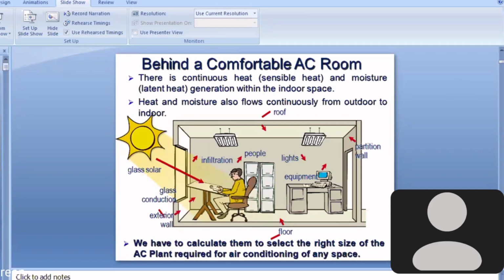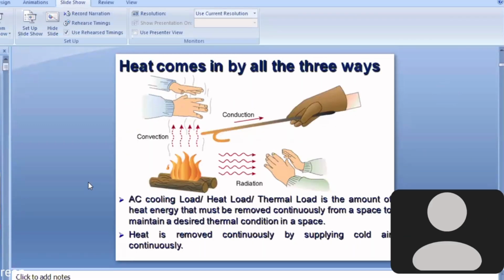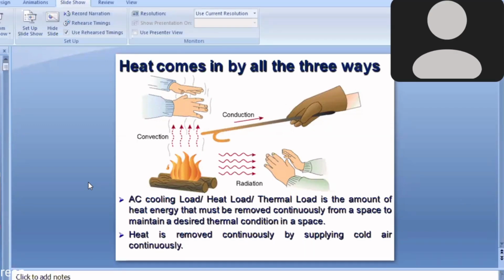The total heat which is being generated inside and the total heat which is coming from outside, all taken together, is called the heat load or the cooling load for an air conditioning plant. The basic objective of today's lecture is to estimate that cooling load. Heat comes in all three ways: by conduction, by convection, and by radiation. This heat is coming in continuously, so we have to remove the heat also continuously.